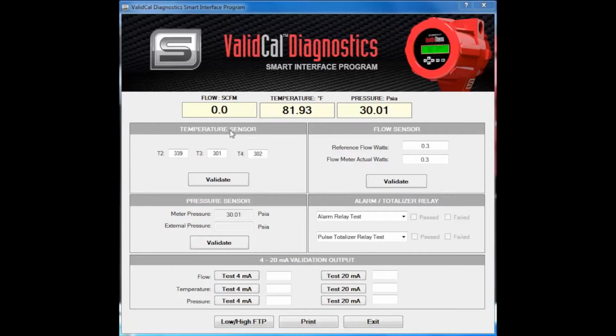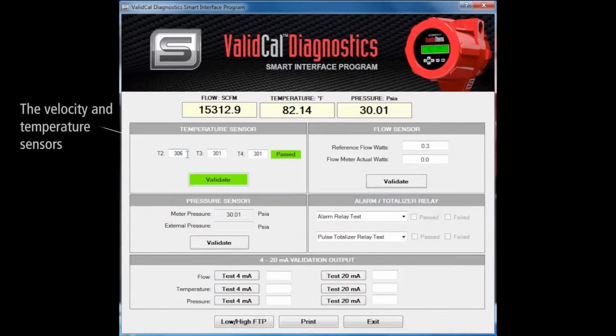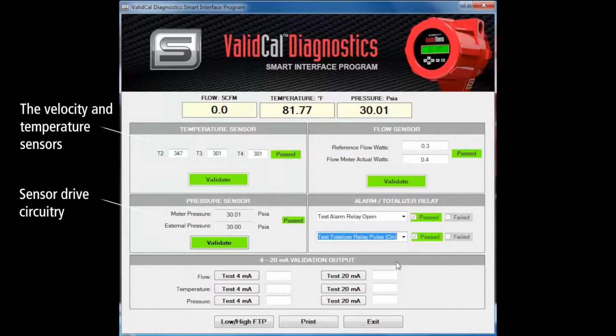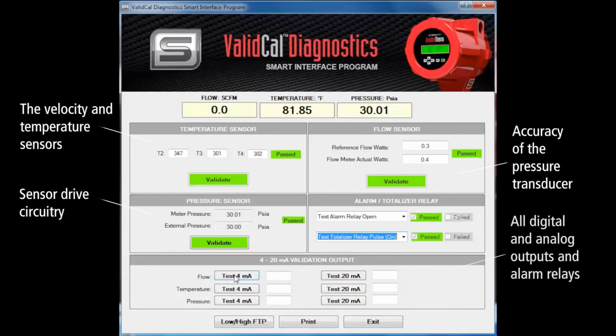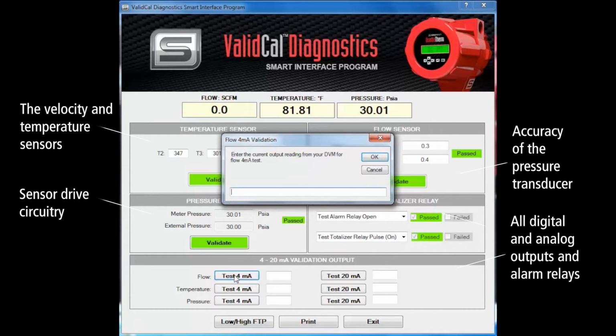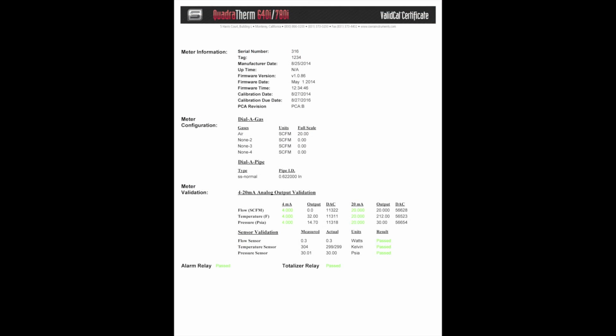Unlike some other validation routines, Sierra's ValidCal Diagnostics program provides a complete check of all the meter's components, including the velocity and temperature sensors, sensor drive circuitry, accuracy of the pressure transducer, and all digital and analog outputs and alarm relays. When complete, a detailed calibration certificate and diagnostics report is created. All of this can be accomplished without even removing the meter from the process piping.